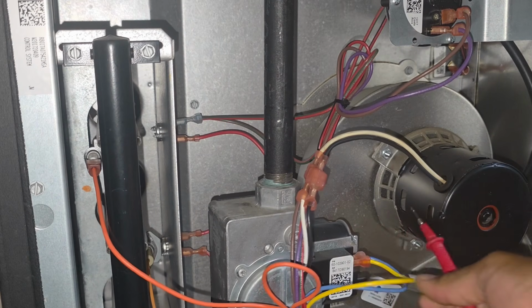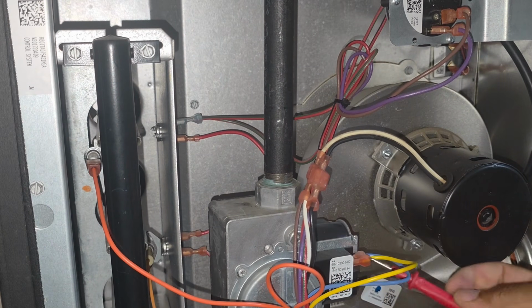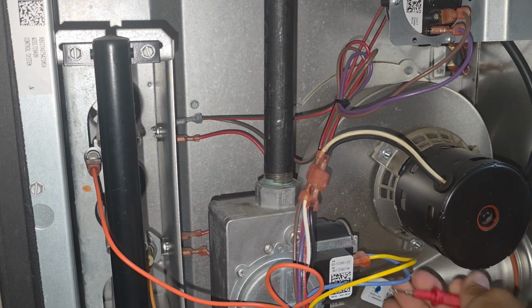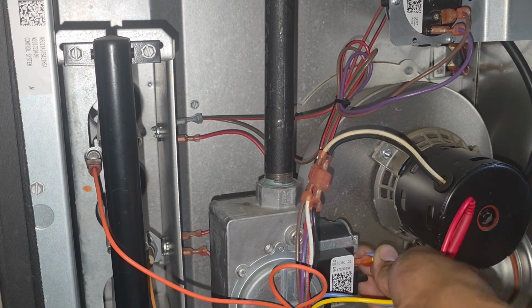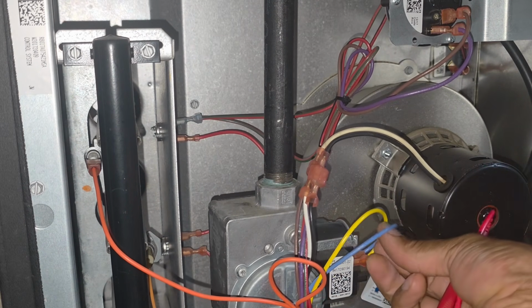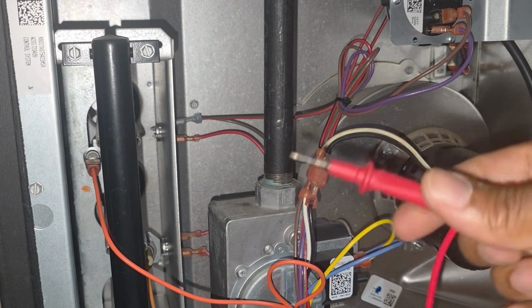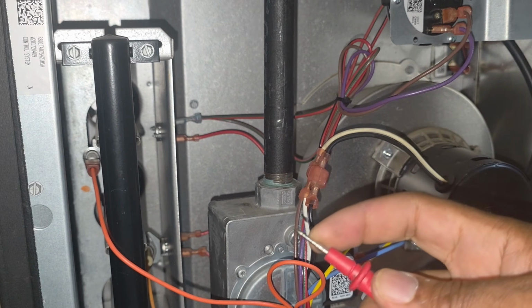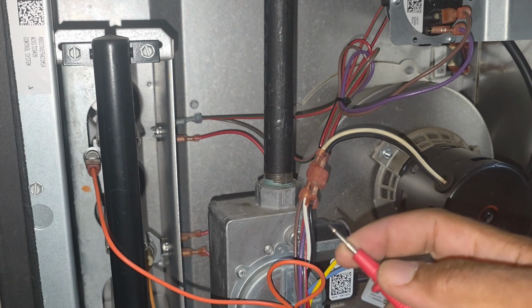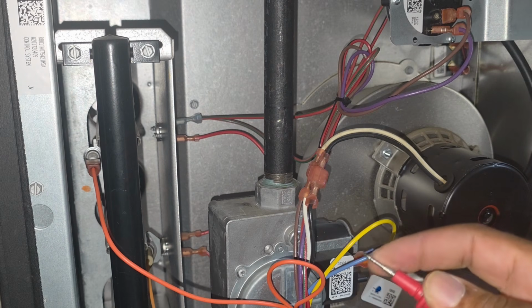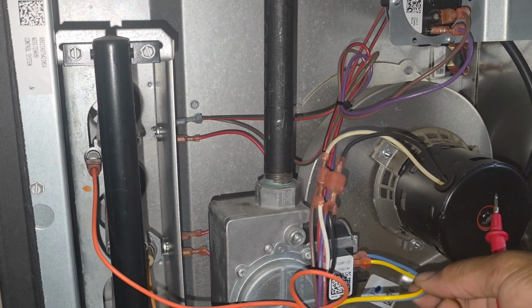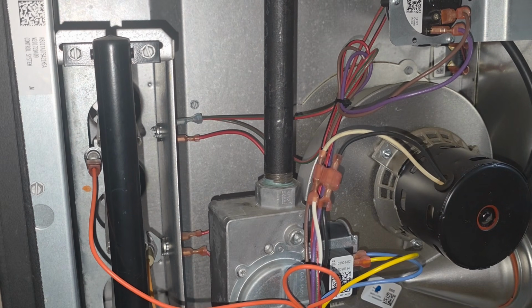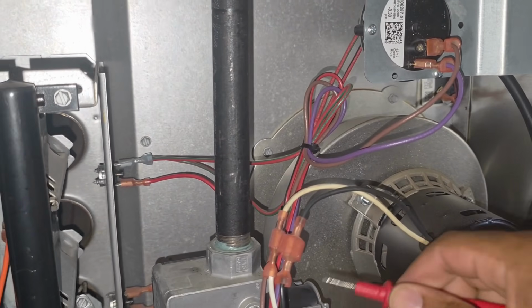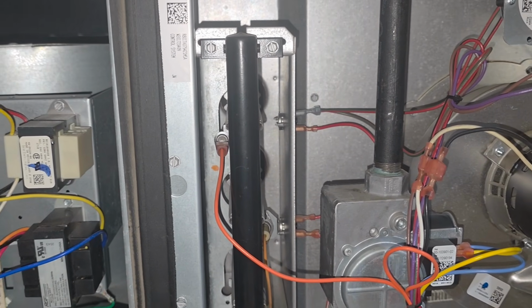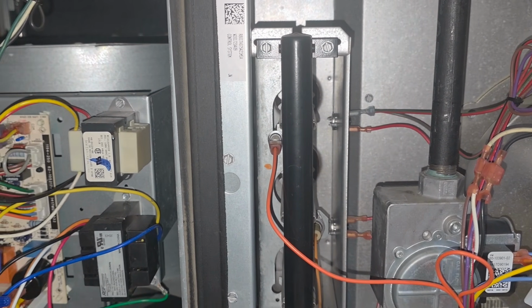You'll try to get in there, get you a good terminal, and see if you're getting 24 volts. Let's see if we can do this. And sometimes you can get these leads right here. You can get them small as a needle thin. But like I said, if you read your schematic, another way you can do it, just say if I couldn't get to these right here, I'm gonna turn the unit back on. We're gonna call for heat.